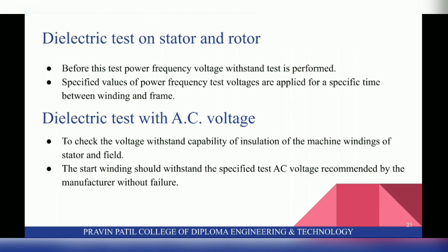Next are the dielectric tests on stator and rotor. Before this test, a power frequency voltage withstand test is performed. Specified values of power frequency test voltages are applied for a specific time between winding and frame. Next is the dielectric test with AC voltage, to check the voltage withstand capability of the insulation of the machine windings of stator and field. The winding should withstand the specified test AC voltage recommended by the manufacturer without failure.